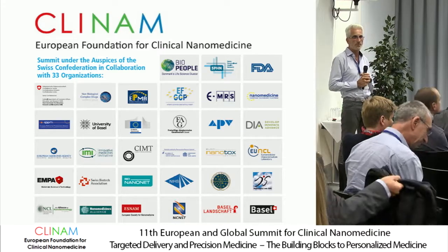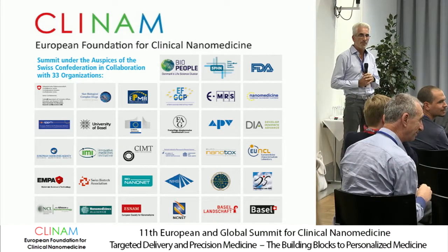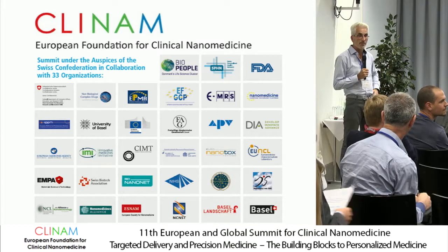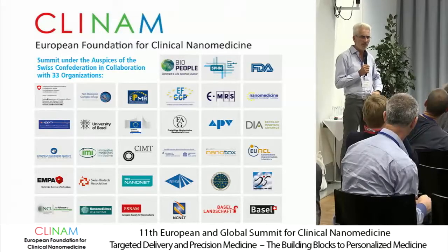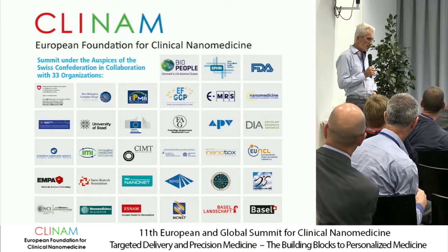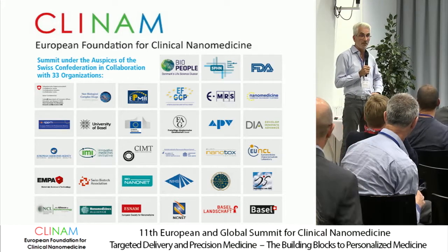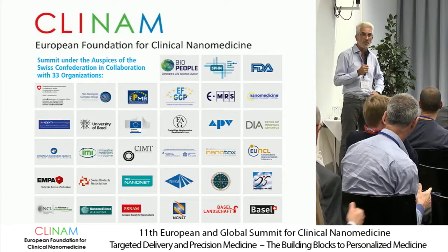But according to repeatability and reproducibility, maybe if we all do the same, we can compare which are more robust or more repeatable. Yeah. But the repeatability of DLS, and I guess it's not only the case for DLS, is really related to the sample complexity. If you take a latex, you have less than 5% repeatability if you use very good standards.